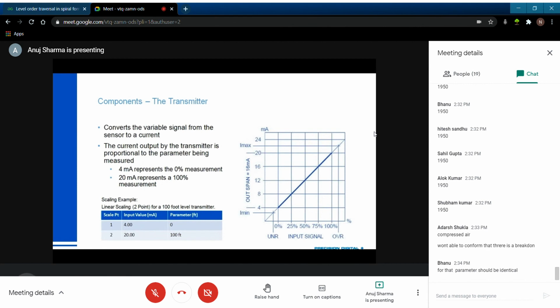The transmitter and the sensor are often the same thing, although sometimes they are different components. You could have a separate thermocouple and a temperature transmitter, for example, that are two different things that could be bought separately, but you could also have a radar level gauge or radar level transmitter, the one device you purchase. The purpose of the transmitter is to take that unique signal that's measuring your process variable and use it to regulate the 4 to 20 milliamp signal.